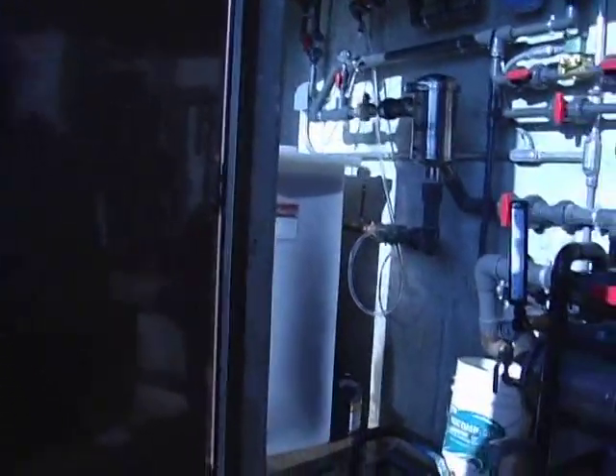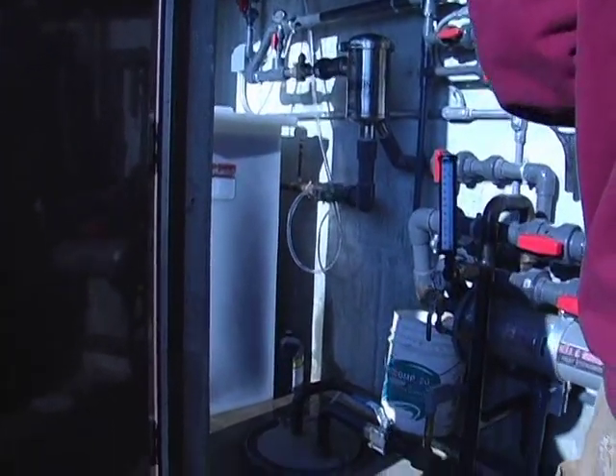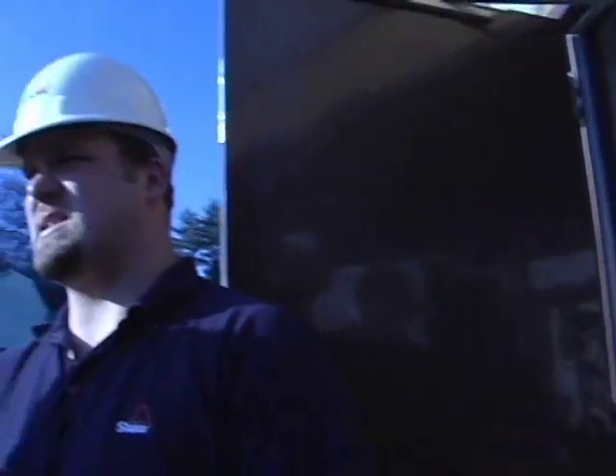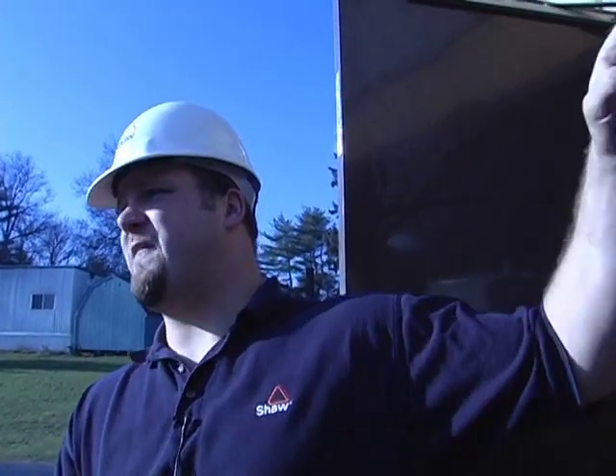I don't know if you guys are ever doing any work in the electrical panel, and this is something that I have seen happen in the past, and it's kind of a common sense thing. If the panel's powered down and this door is open, the main feed coming into that panel is still hot. So under no circumstances should you try to adjust anything coming off the main electrical feed going into that panel unless the main power is off. I have seen people shock themselves pretty bad, and with 480 going into this panel, you'll be lucky to live if that happens.